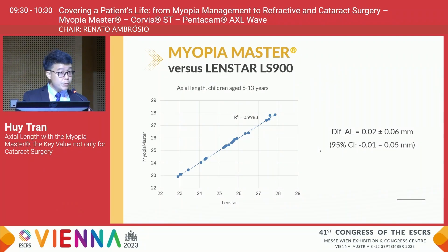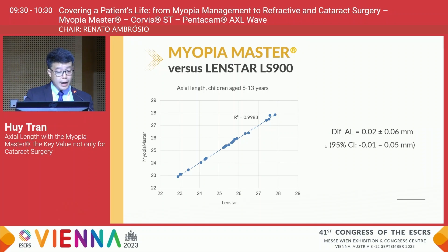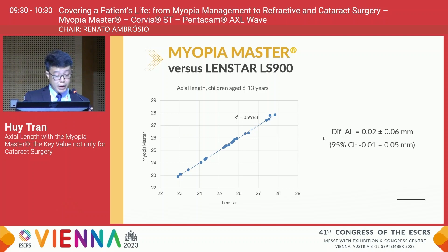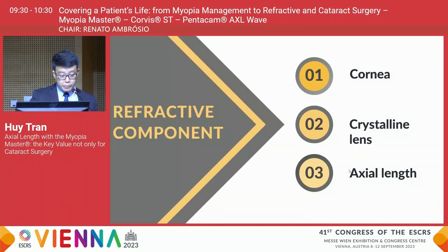To review the repeatability and reliability of Myopia Master measurements, we compared a sample of measurements from our Myopia Master system with another biometer. In children aged 6 to 13 years old with myopia, the difference between the two devices was quite substantially low. The mean difference of axial length was about 0.02 millimeters, with a 95% confidence interval ranging between −0.01 to 0.05 millimeters.